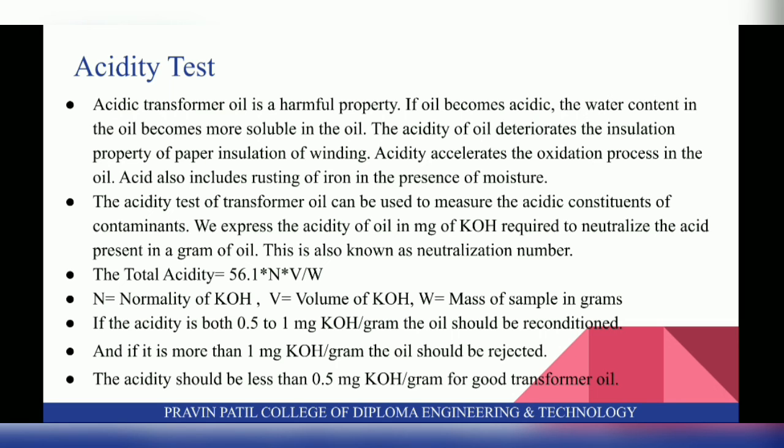If the acidity is between 0.5 to 1 mg KOH per gram, the oil should be reconditioned, and if it is more than 1 mg KOH per gram, the oil should be rejected. The acidity should be less than 0.5 mg KOH per gram for good transformer oil.